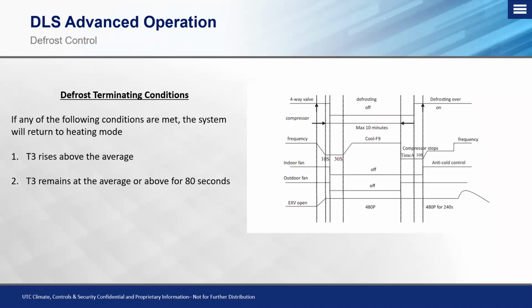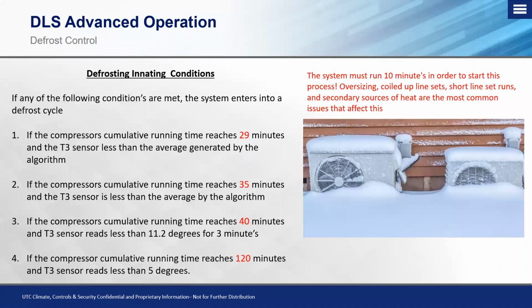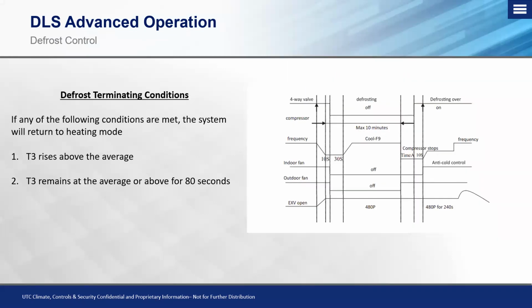Now we know what starts the defrost, and we know the minimum amount of time that we have to run before it starts looking at those conditions, but what takes it out of defrost? Okay, well, the first one's going to be if that T3 or that outdoor coil sensor rises above that average. So if we take a look back on here, we see if that sensor is less than that average, we know, okay, hey, we're going to kick it into a defrost. That same average controls as that T3 sensor rises above that average on there. Okay, so if that T3 remains at that average temperature or above for 80 seconds, that's when we're going to go ahead and consider that defrost successful and take it out of defrost to return to normal operation.